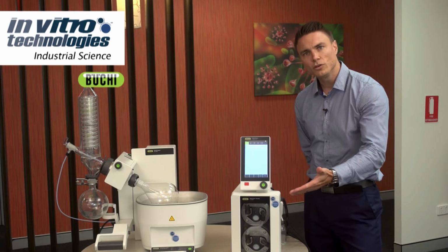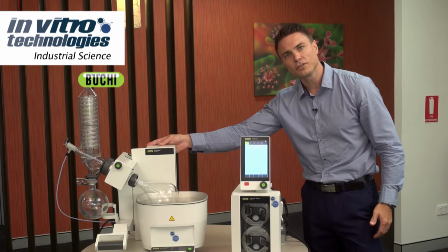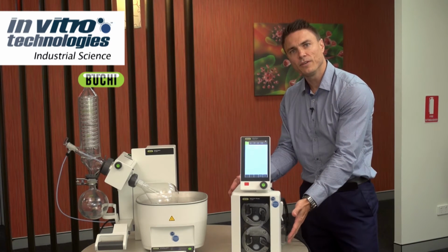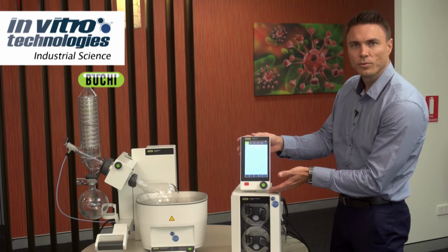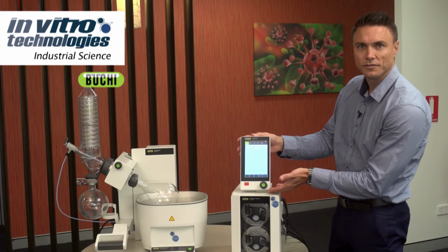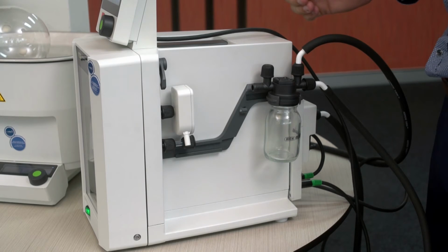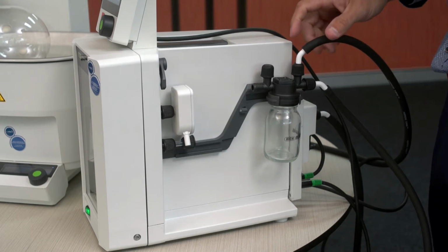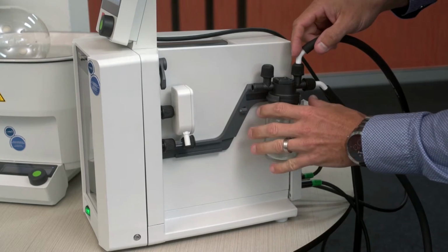Today we're going to talk about the new Buchi units: Rotary Evaporator Electronic R300, Vacuum Pump V300, and I300 Pro Digital Touchscreen Control Interface. Here we have the Buchi V300 Vacuum Pump. It is a two-stage, two-head, Teflon-lined diaphragm vacuum pump, so oil-free.